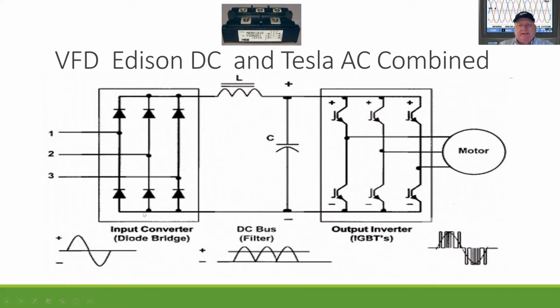Then what a VFD is, it's basically a diode bridge, meaning a three-phase bridge that lets current pass one direction. And so the ultimate resulting power ends up all being inverted. Instead of being sinusoidal, it flips these waveforms onto the top, and it gives us bumpy power. And then they put capacitors in here, and those capacitors are various sizes. What that does is help smooth things out, so we get clean DC power.